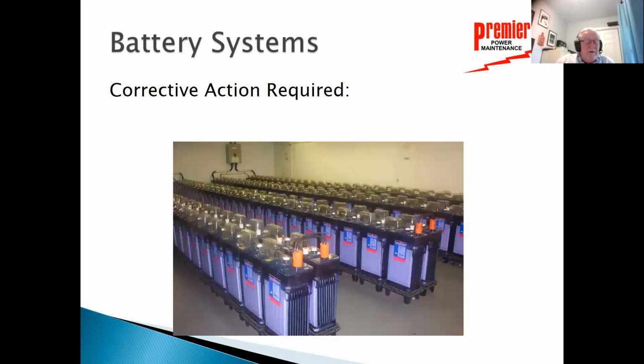When are corrective actions required on this battery system? Well, anytime the visual inspection doesn't look good, that's an indication that we need to do some corrective action. If the terminal resistance of any one of those terminals is 20% above the installation value, or if it varies by 20% over sister cells in that same unit, then that's a problem.